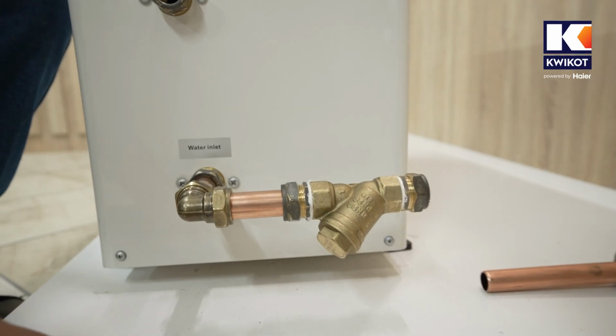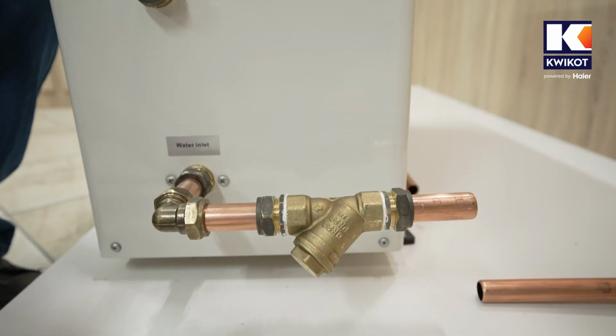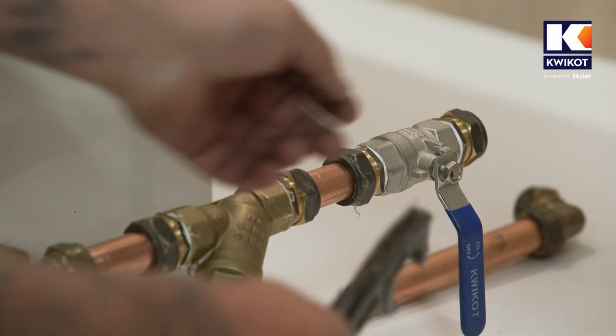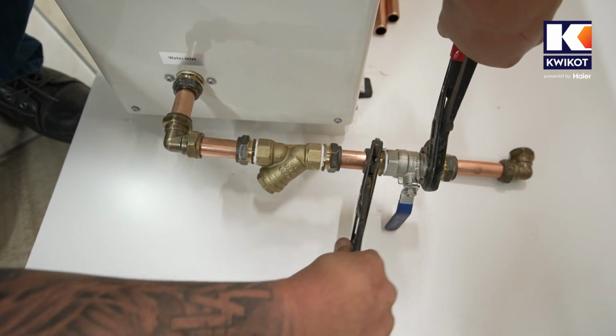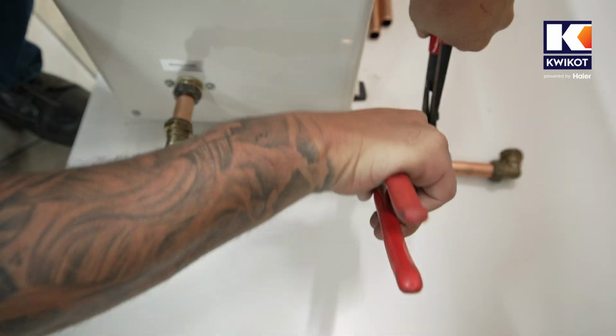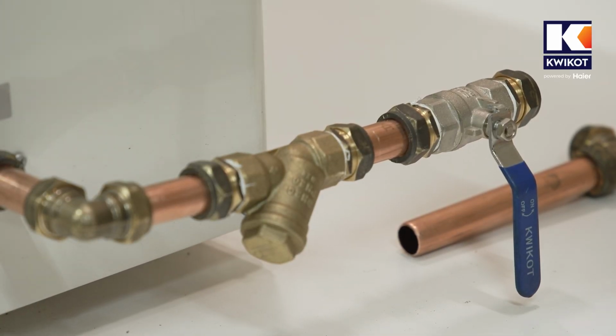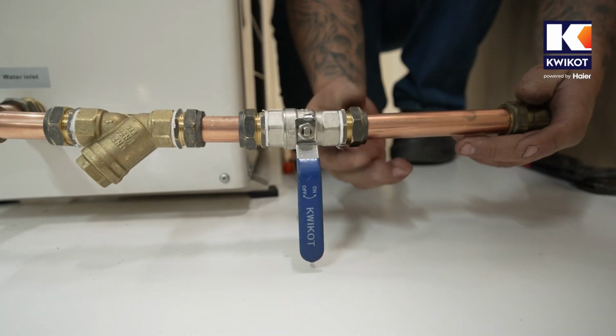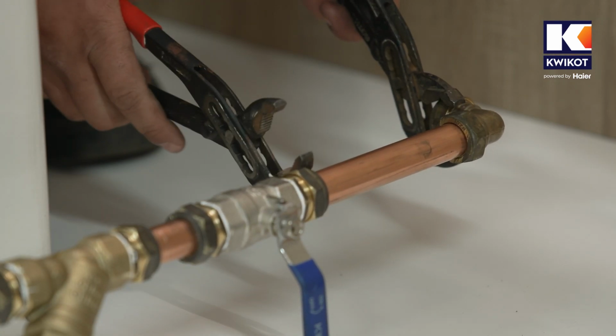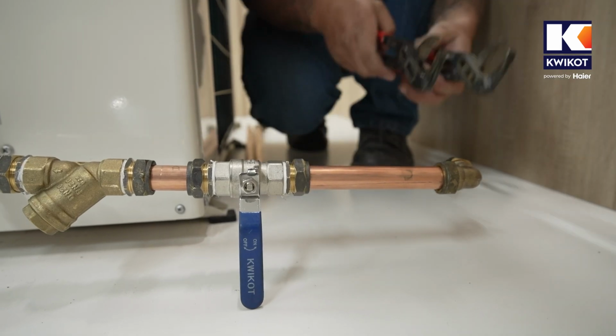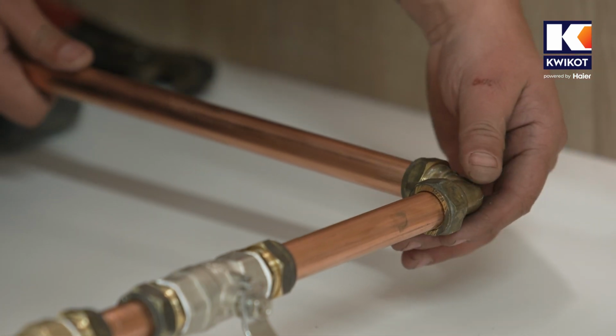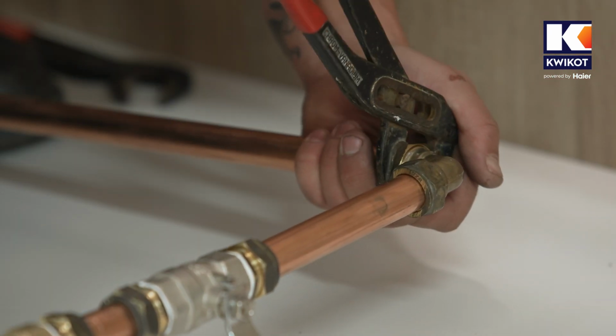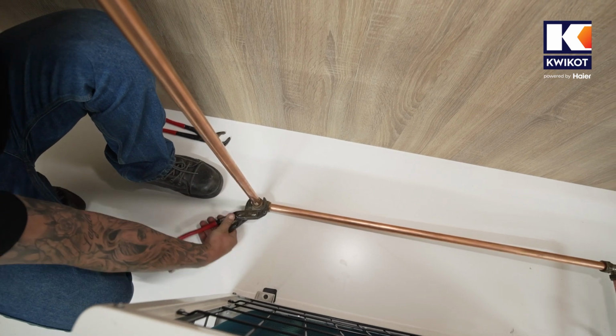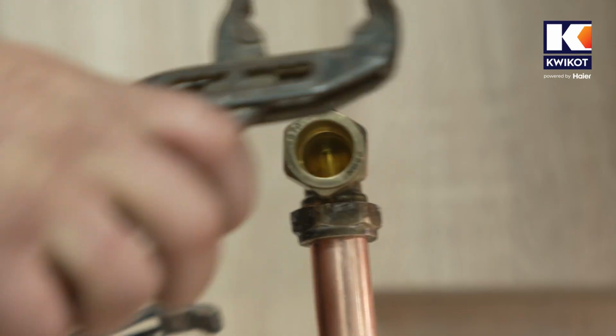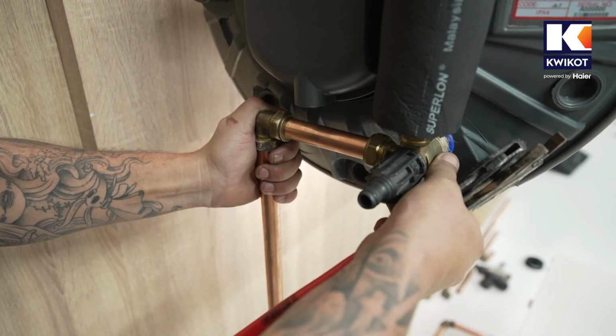And then we tighten up the join, add our third length of pipe, and fit the lever valve. This will allow us to shut off the water flow when you want to clean the strainer without having to drain or isolate the water heater. We will also fit another lever valve on the hot side, and now we fit another elbow. So we're not going to tighten this side of the lever valve because we still need to apply lagging to this copper pipe. And then we fit another longer length of pipe and another elbow to run a final length of pipe up to the water heater. So now your cold pipe running to the heat pump is connected to this double drain cock.